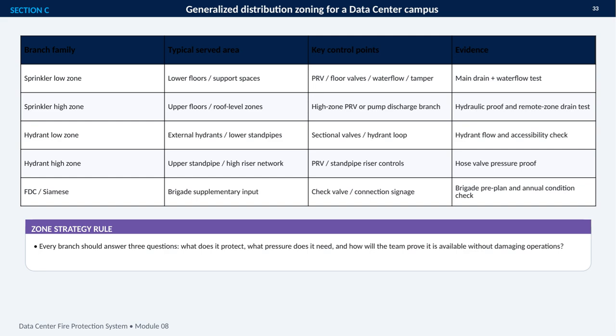For sprinklers, the low zone typically serves lower floors and support spaces, with control through pressure-reducing valves, floor valves, water flow devices, and tamper switches. The high zone serves upper floors or roof-level areas, where pressure may require a dedicated valve arrangement or pump discharge branch. Hydrant zones follow the same logic, separating external hydrants and lower standpipes from upper standpipes and high riser networks.